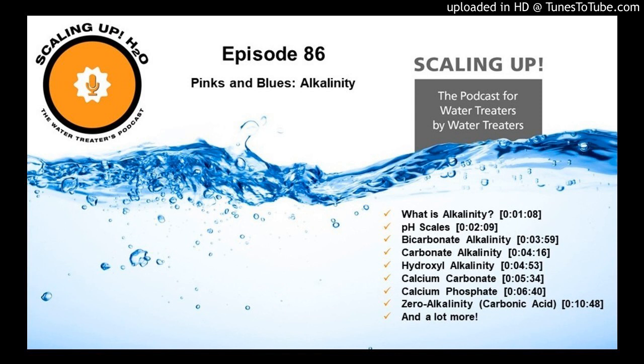If there's one thing that we have in water treatment, it's multiple terms. And I know that's really difficult for somebody learning because we'll learn something one way and then we'll be introduced to another term. Well, folks, just get used to it. We have multiple terms for everything in water treatment. I don't know why that is, but that is how it is. All right, so now we go to 10.3 and above. Above 10.3-ish, we have hydroxyl alkalinity. So those are the 3 alkalinity species that we have, and then our water treatment products are built based on that.